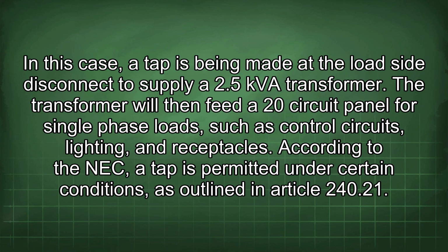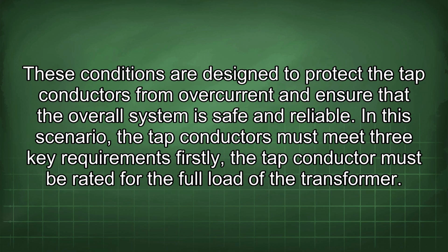According to the NEC, a tap is permitted under certain conditions, as outlined in Article 240.21. These conditions are designed to protect the tap conductors from overcurrent and ensure that the overall system is safe and reliable. In this scenario, the tap conductors must meet three key requirements. Firstly, the tap conductor must be rated for the full load of the transformer.